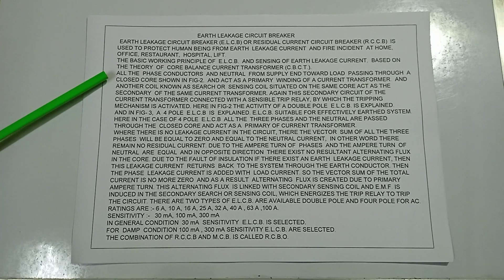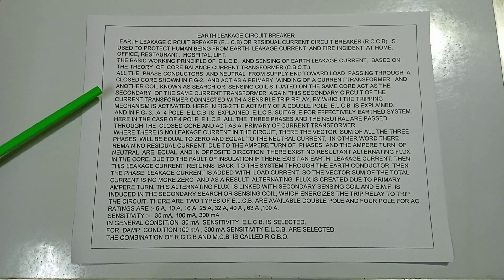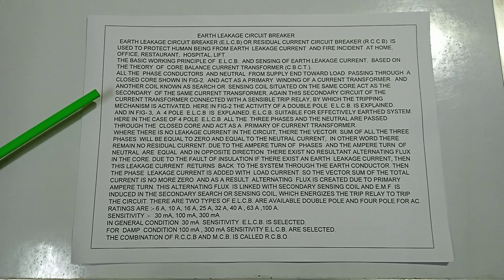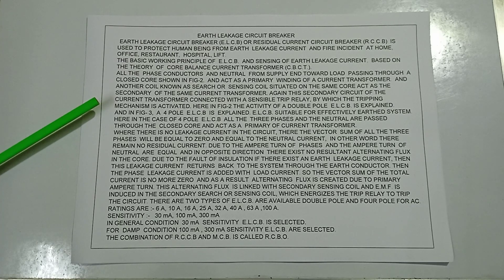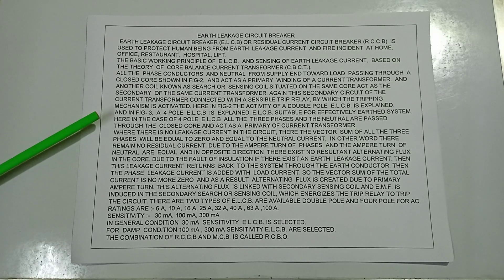All phase conductors and the neutral from the supply end toward the load pass through a closed core, as shown in Figure 2, and act as the primary winding of a current transformer. Another coil, known as the search or sensing coil, situated on the same core acts as the secondary of the current transformer. This secondary circuit is connected with a sensitive trip relay by which the tripping mechanism is activated.